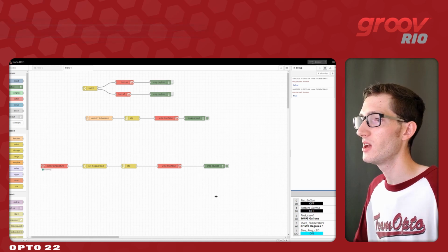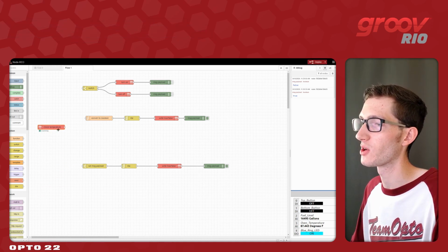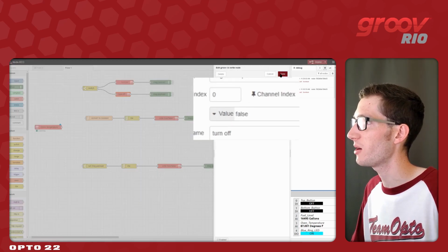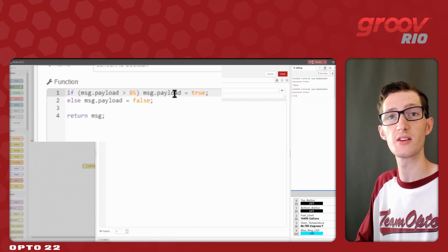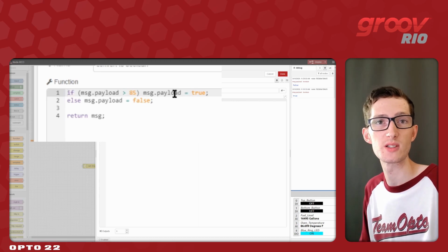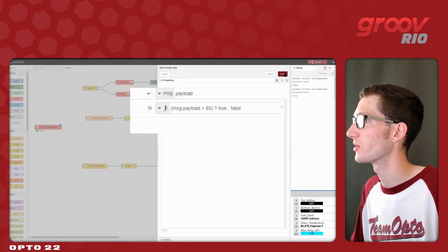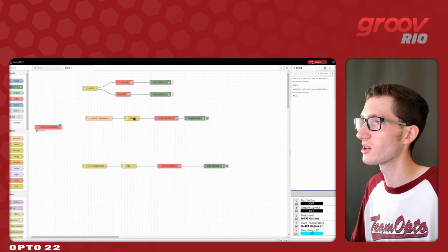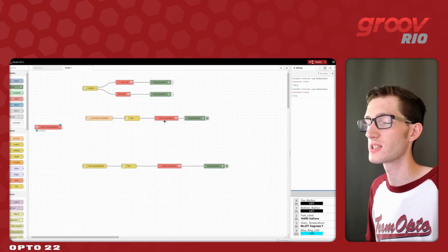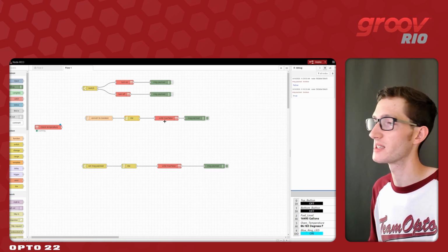So here you can see we have three different methods of control. We have the switch node that can redirect traffic and write a constant value of true or false to our digital output. We also have the option to use raw JavaScript code, which you can also use more advanced functions. If that's something you're interested in, we'll have some links in the descriptions of some great places to get more familiar with JavaScript. Or you can just use a simple JSONATA expression to keep it nice and contained in this change node. Whatever approach you take, you might want to consider using these report by exceptions so that you can block the value unless it changes, so that there's a little bit less weight on your writing nodes, and that'll free up your API to do other things.